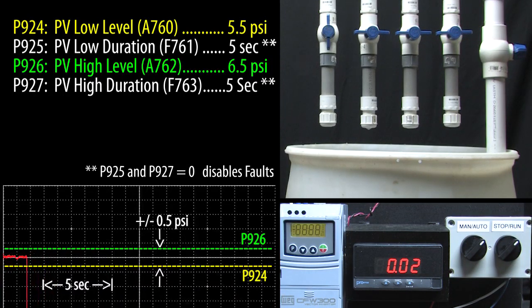I remove the short to ground so I'll reset the fault, which resets the drive and since the run switch is still enabled, PID starts right back up, we get the low pressure alarm until the pressure ramps up and everything is back to normal.